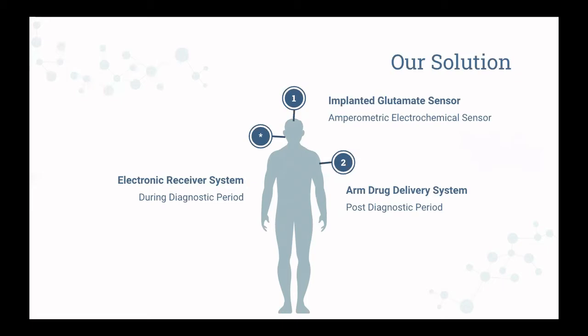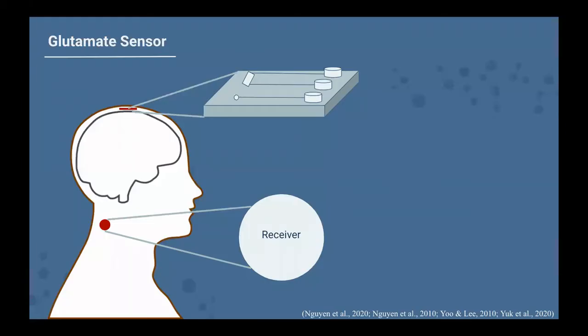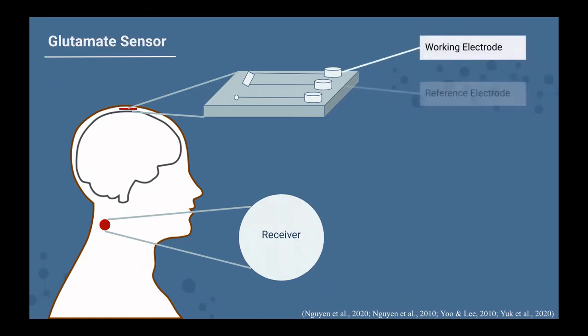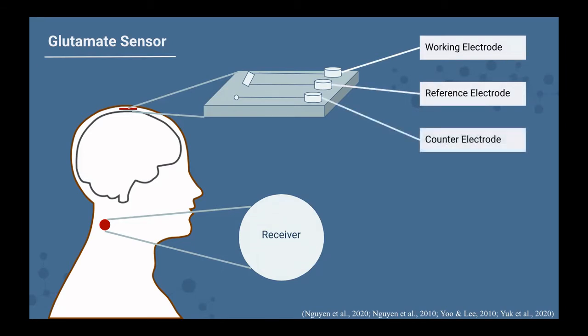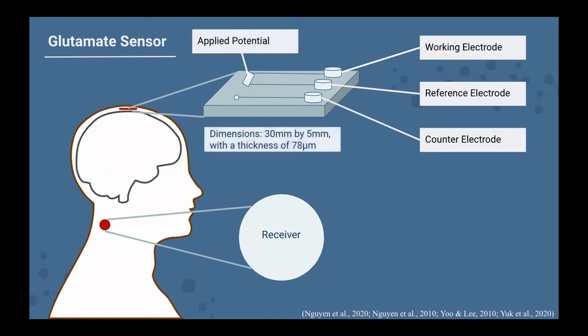Our biosensor is an amperometric sensor which monitors current generation when electrons are exchanged between a biological receptor and an electrode. The biosensor has a polymer base with 3 electrodes. The working electrode is where the current is measured. The reference electrode is used to measure the working electrode by maintaining a constant electrochemical potential, and the counter electrode is an inert conductor to complete the circuit. Our device has an applied potential of 0.5 volts with reference to silver chloride to obtain the current reading. Based on dimensions of similar intracranial devices, ours will be 30 millimeters by 5 millimeters with a thickness of 78 micrometers. The sensor will be surgically implanted in the subarachnoid space in the brain through a robotic procedure.